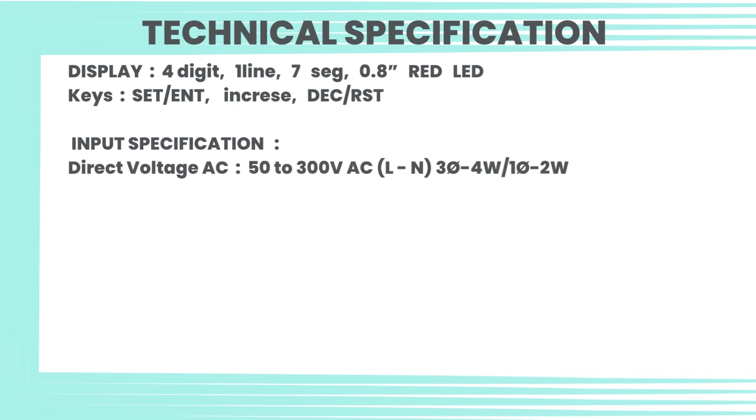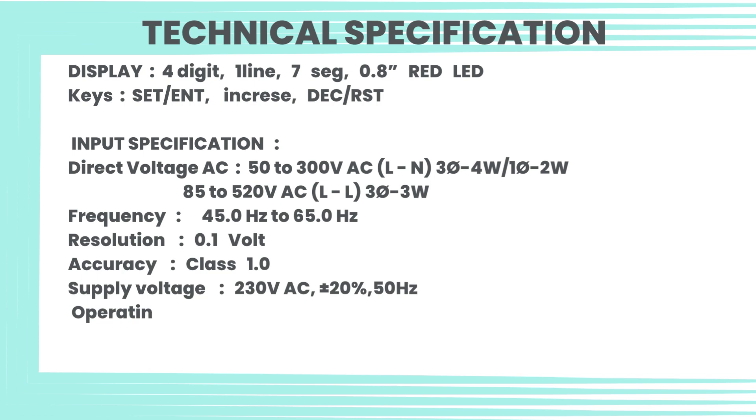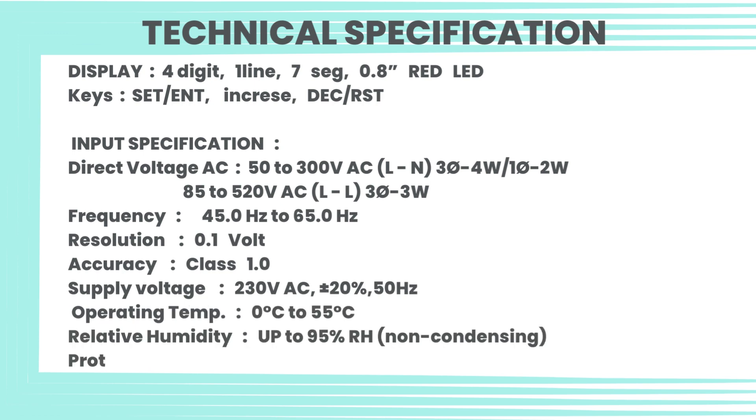Input specification — Direct voltage AC: 50 to 300V AC (L-N), 3ø-4W / 1ø-2W; 85 to 520V AC (L-L), 3ø-3W. Frequency: 45.0 Hz to 65.0 Hz. Resolution: 0.1 volt. Accuracy: class 1.0. Supply voltage: 230V AC ±20%, 50 Hz. Operating temperature: 0°C to 55°C.